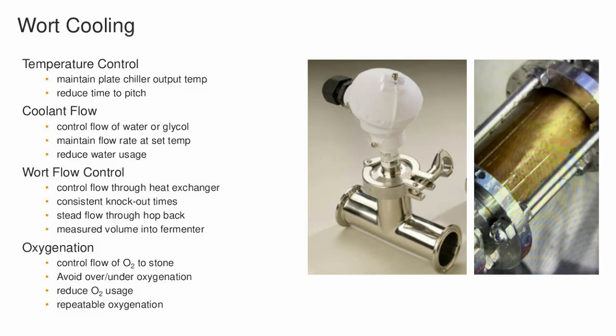If you're really targeting a 45-minute or 30-minute cool down, you're going to set your volume flowing through, and you can monitor that with a flow meter, or you can do a loop on that so it will automatically control the flow. Typically you want that flow to be constant, and then put the control loop on the water flow. That water flow will be based off the temperature probe pictured there, on the output of the chiller. So your control loop runs in that way.